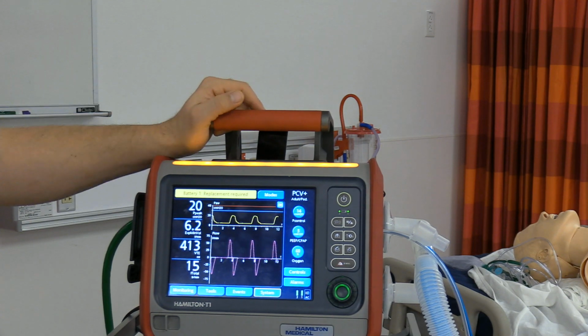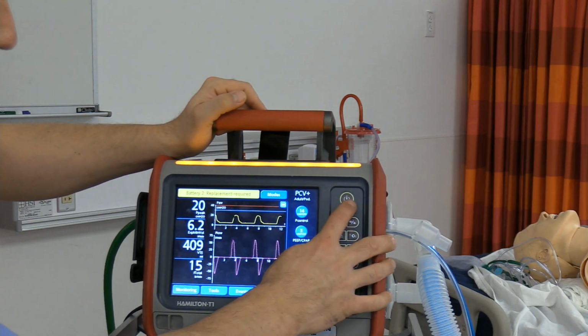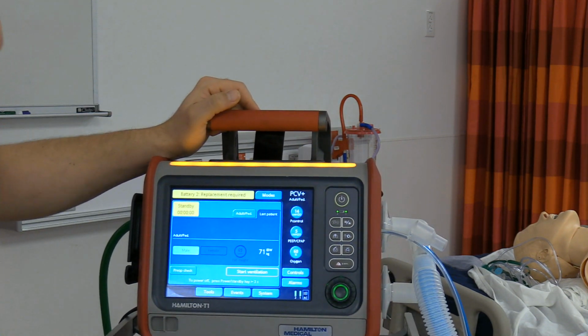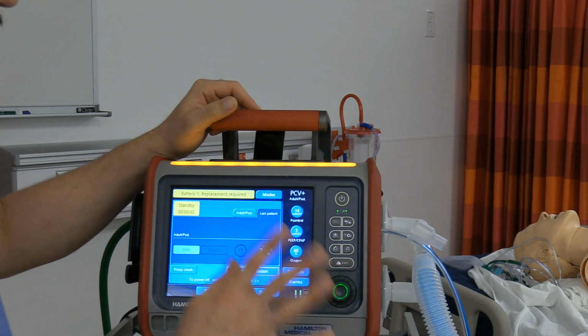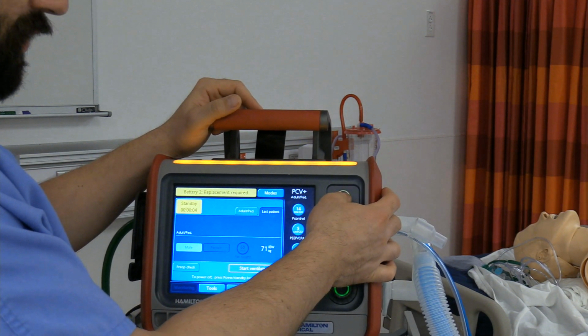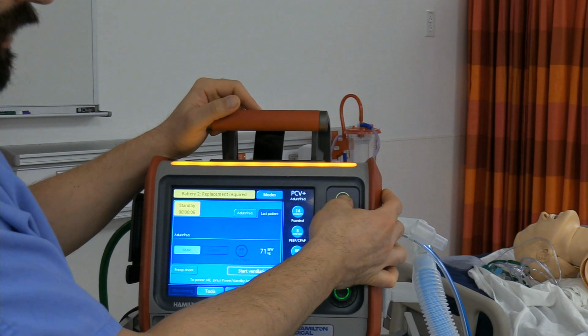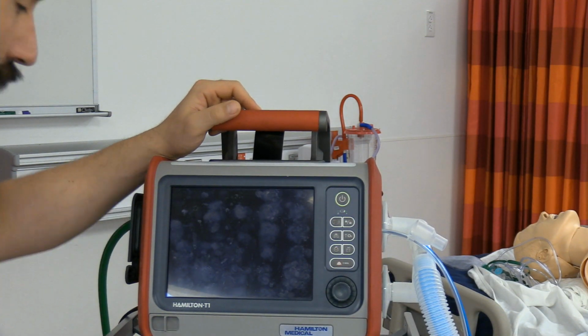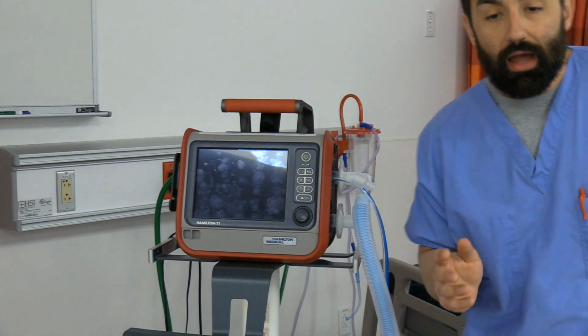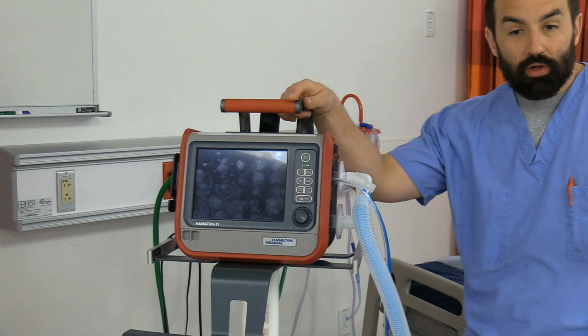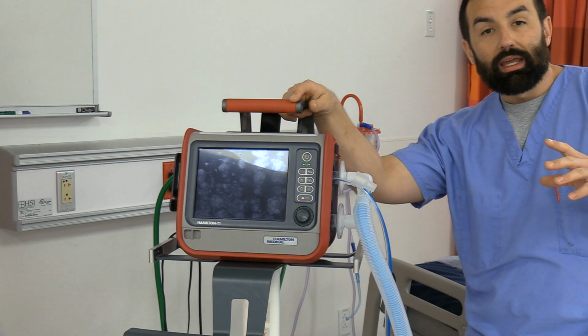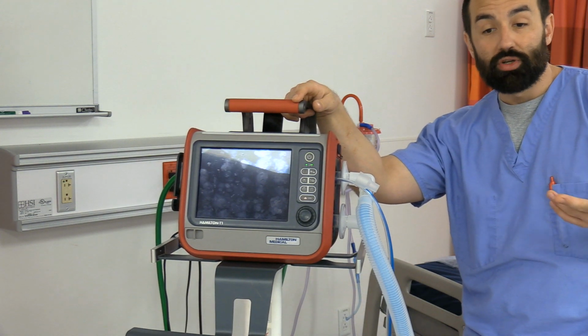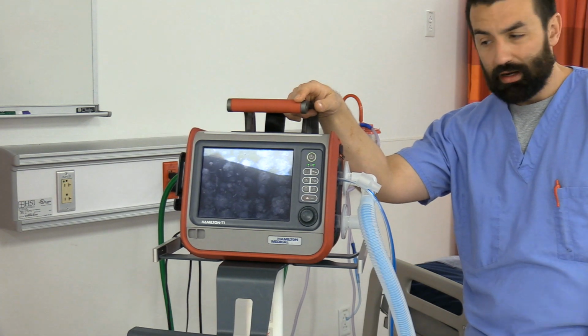I'm going to go ahead and show you how to put it in standby. So I'm going to go ahead and hit the power button again. Activate standby, so no longer giving gas to the patient. I could leave it in this screen, or I could press and hold this for 3 seconds, and it's going to go ahead and shut off. So that serves as a pretty good overview here of setting this ventilator up, as well as showing you how to really do the pre-use check, in addition to initiating pressure ventilation in a very abridged version there.